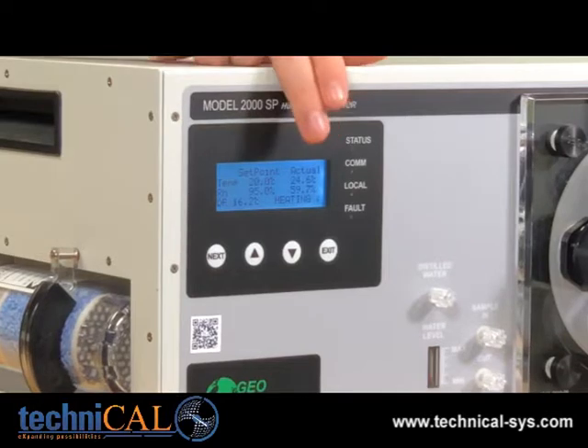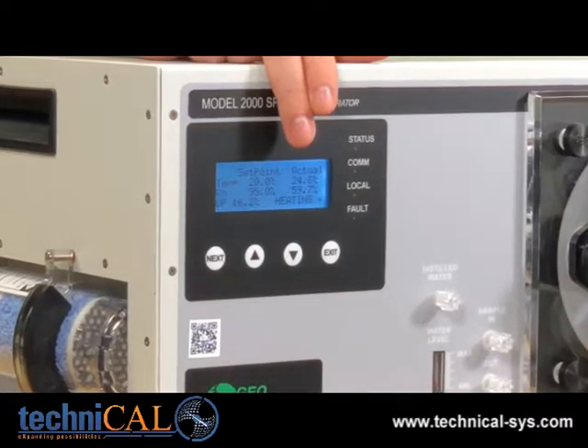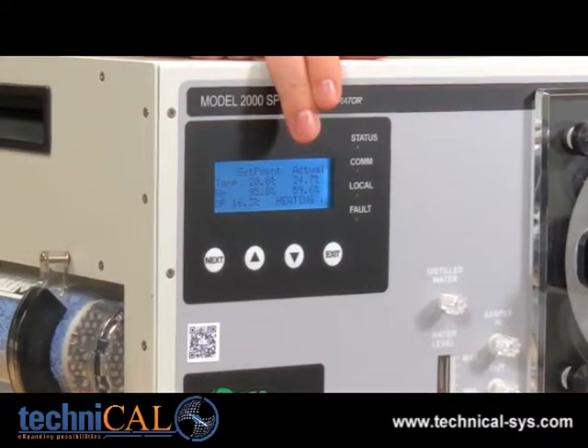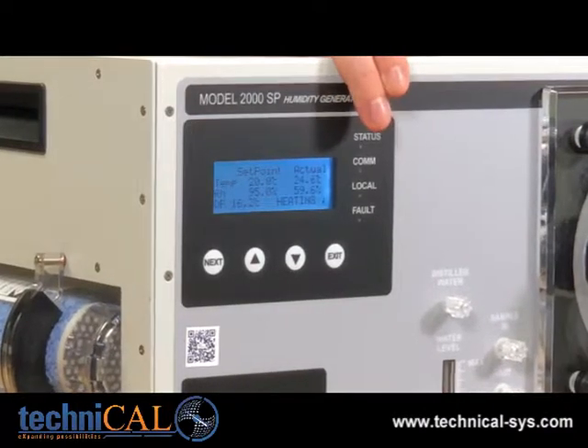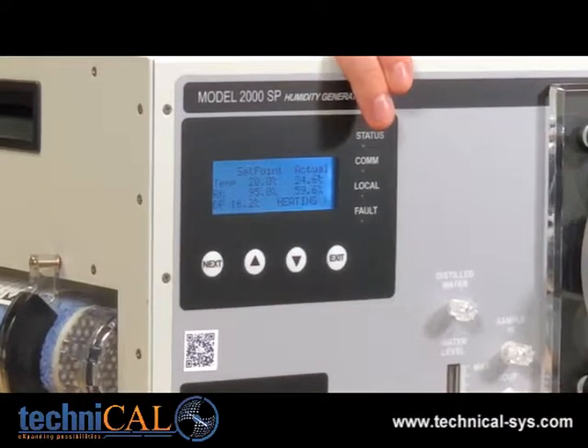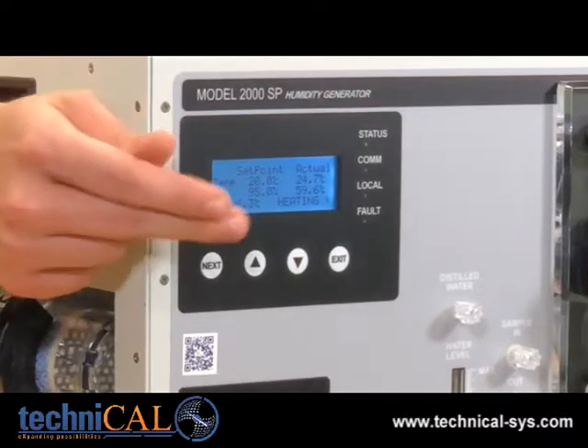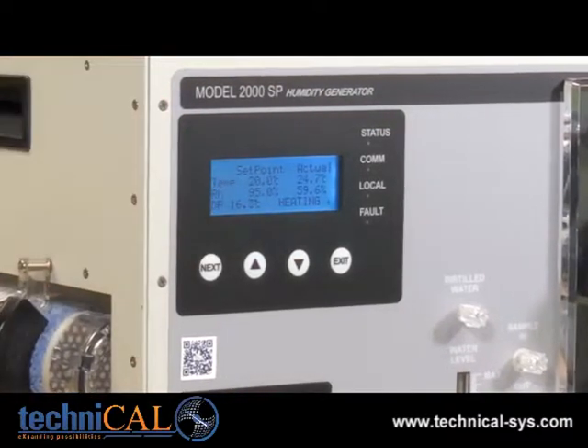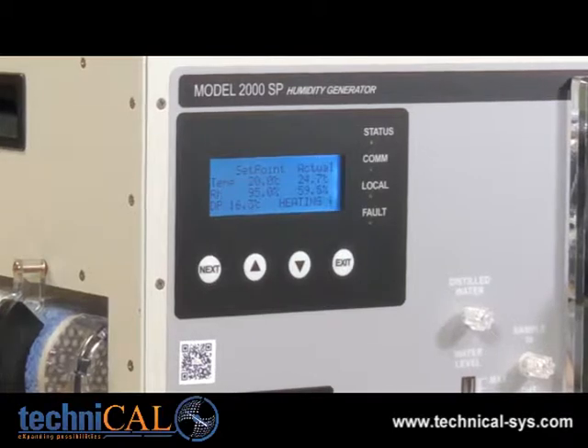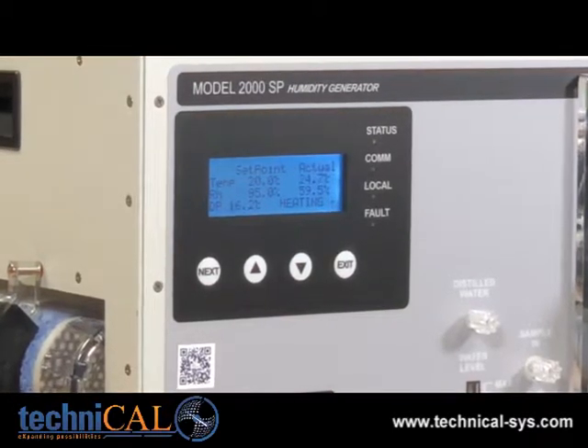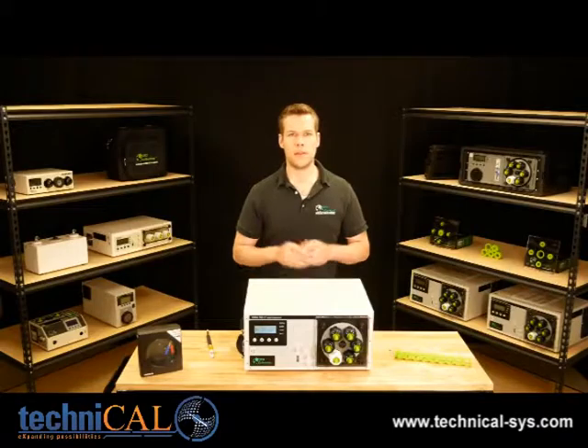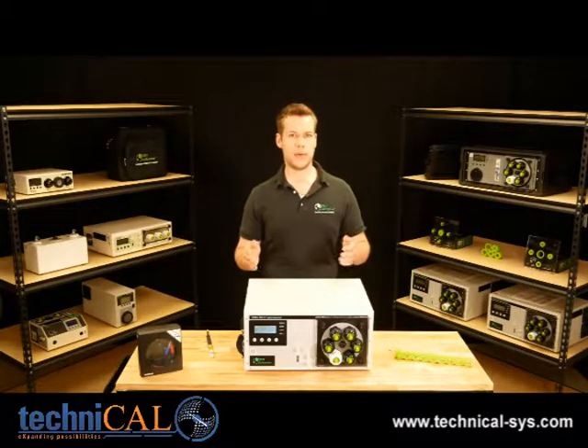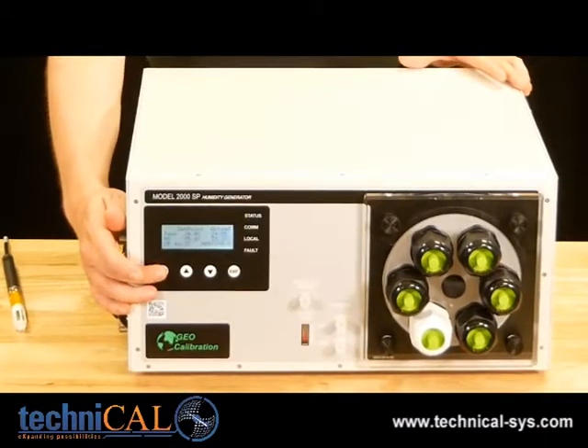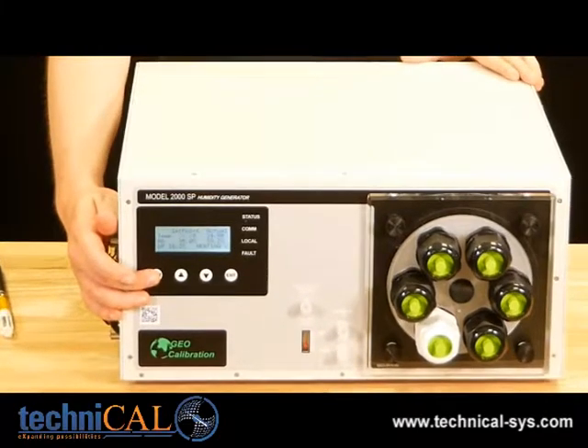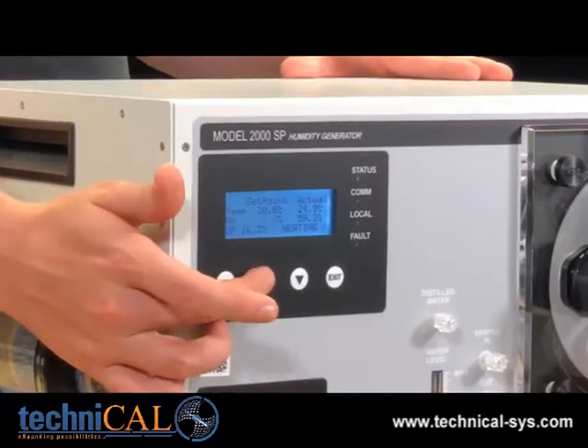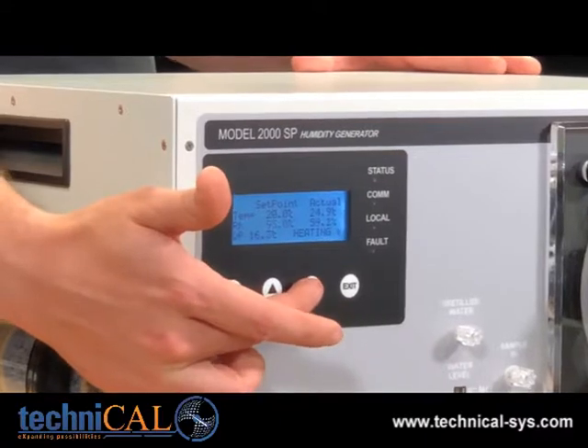Changing focus back to this unit's display, we can see that it contains 5 values in total. On the left, we can see the user-entered temperature and humidity set points, while on the right, we can see the actual temperature and humidity as measured by the internal capacitive standard. Finally, on the bottom, we can see a calculated dew point, which is very useful if you're using a chilled mirror or operating at an extremely high humidity percentage. To change the set points, all you need to do is press the next button to toggle between humidity and temperature, and then hold either the up or down buttons until you reach your set point.